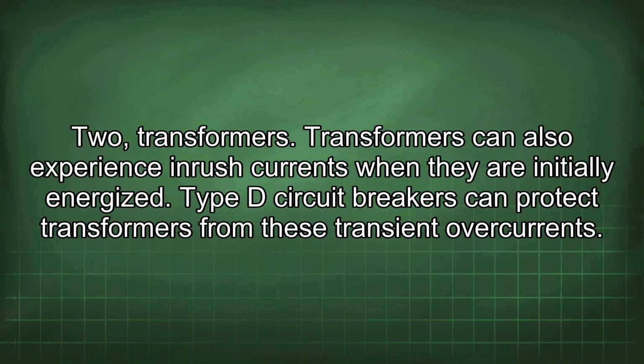2. Transformers. Transformers can also experience inrush currents when they are initially energized. Type D circuit breakers can protect transformers from these transient overcurrents.